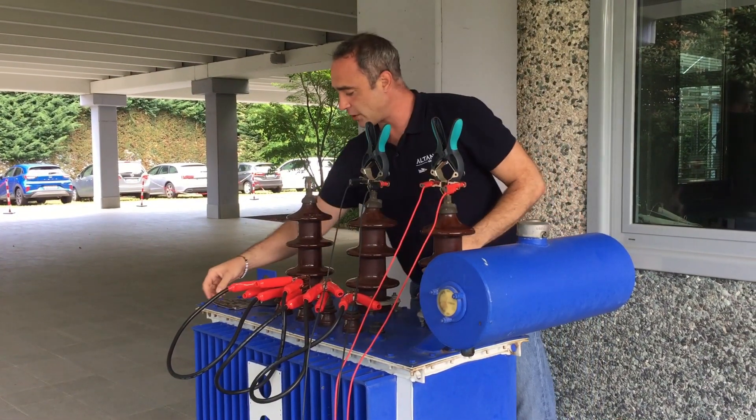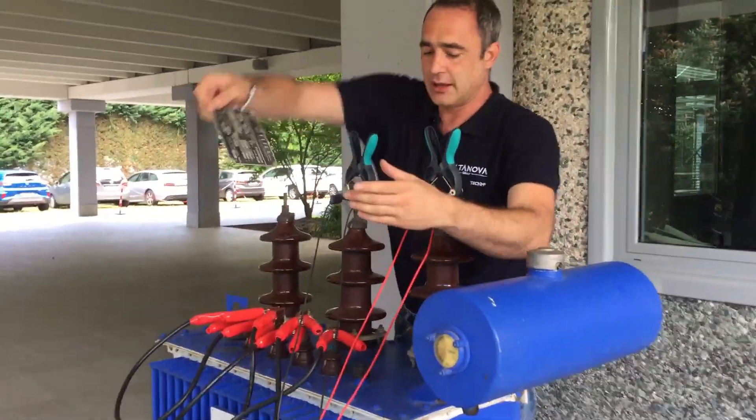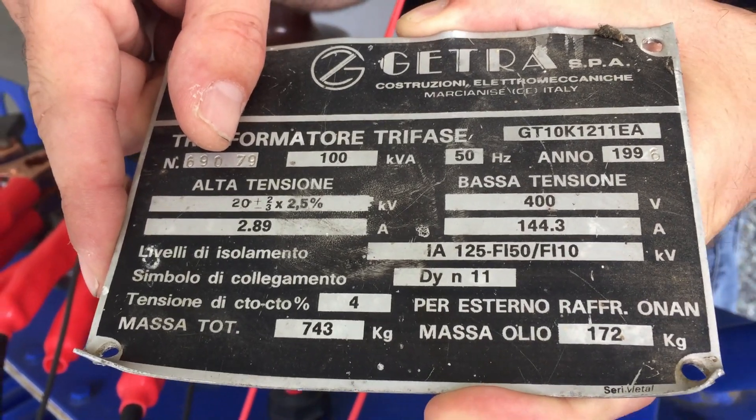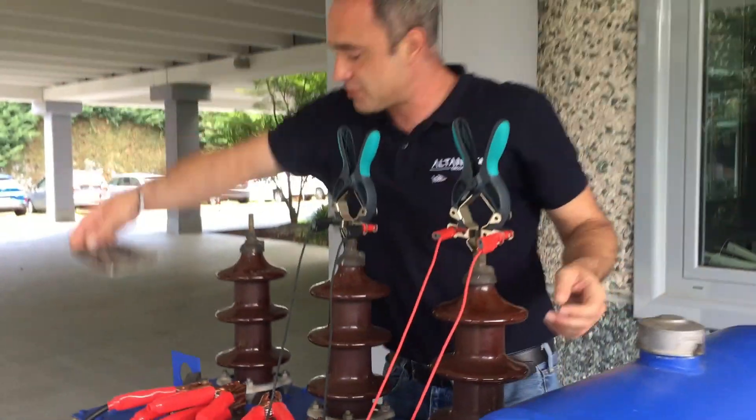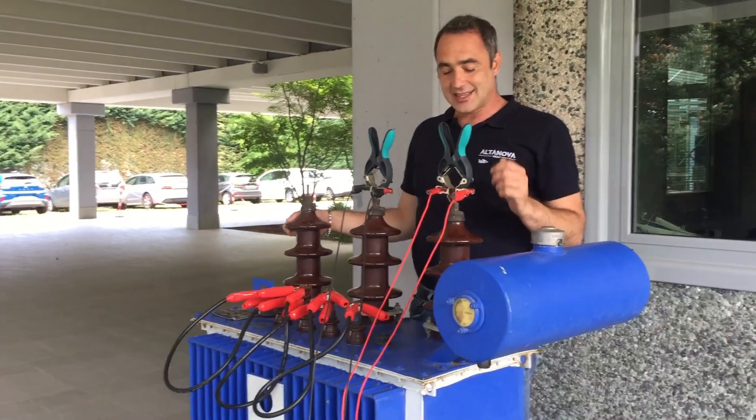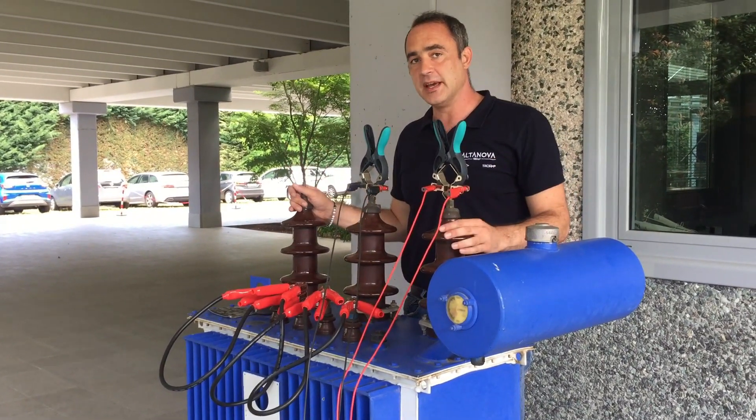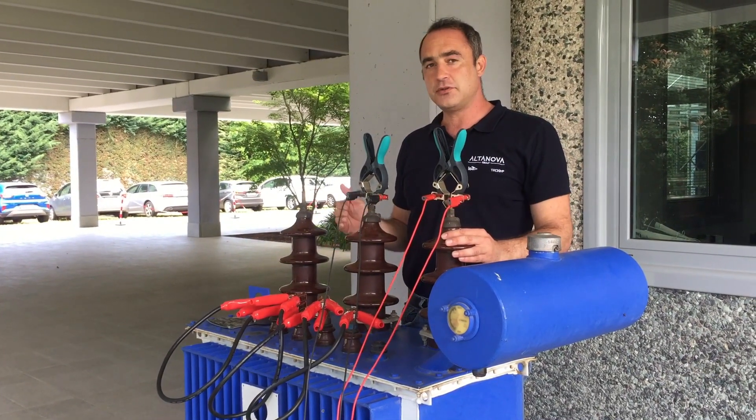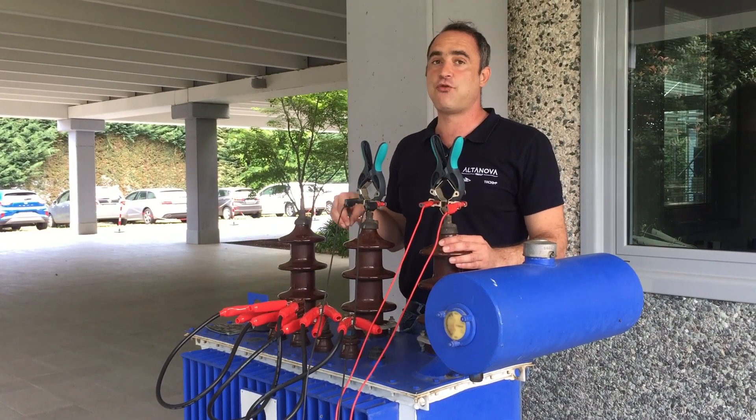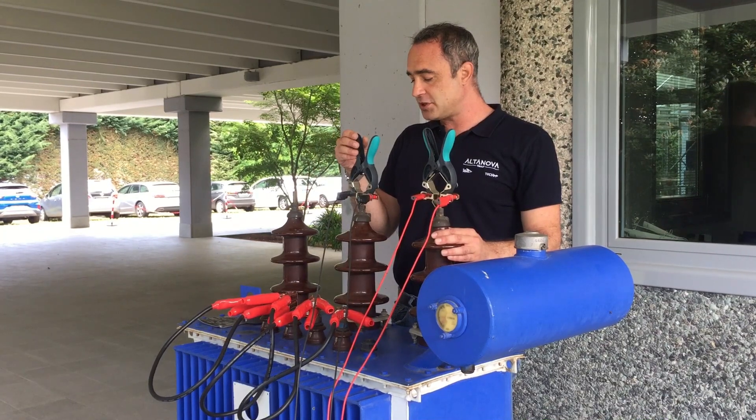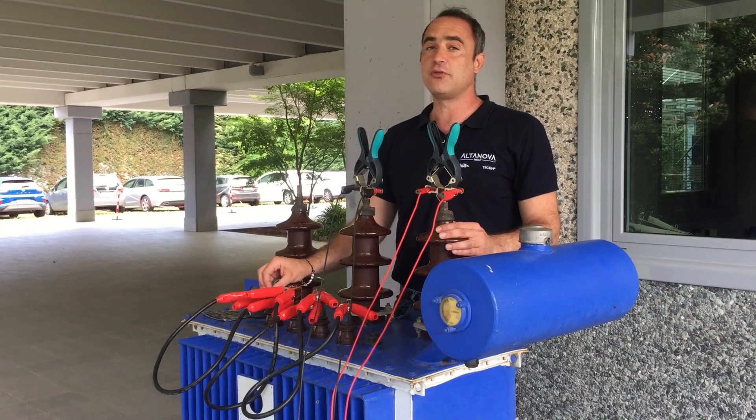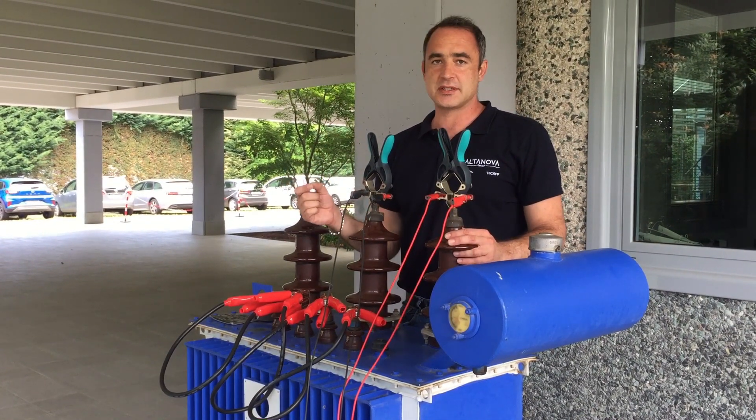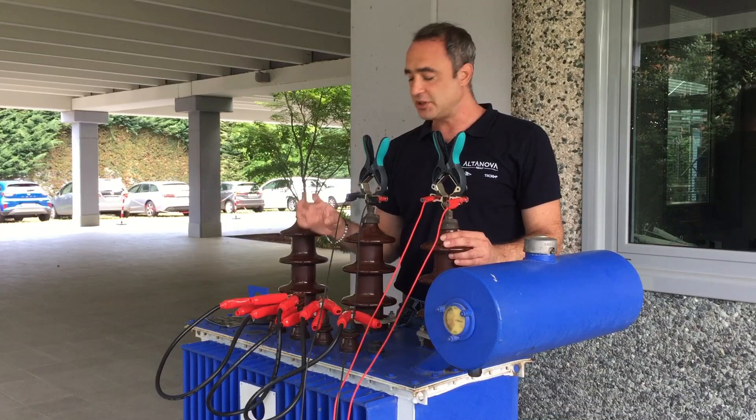Before we start the test, I want to show you that we have a nominal data here and it says 4%. So 4% is my nominal value for this transformer. What this means is that if this is a 20 kilovolt to 400 volt transformer, I actually need to generate not 100% but 104% of primary voltage to get the nominal voltage on the secondary side because 4% will be lost due to the copper resistance in the windings. So these are the losses.